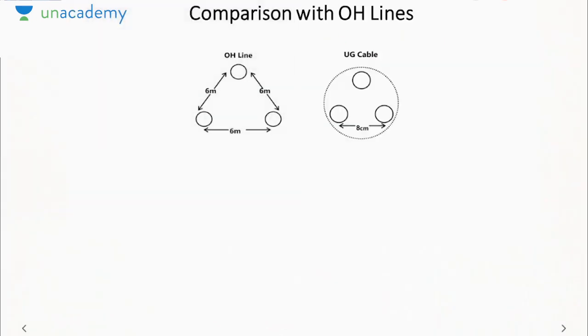Next, let us compare the performance of overhead line with the underground cable. Now the essential difference between the overhead line and the UG cable is the distance between the conductors. Whenever you are making all three conductors in a single cable, you have to keep less distance between the three conductors. Otherwise the radius of the cable would be very high, which is impractical. Like if you keep the distance 8 meter, then the radius of the cable will be so high that you cannot manufacture and transport the cable. So the distance reduces in case of a UG cable.